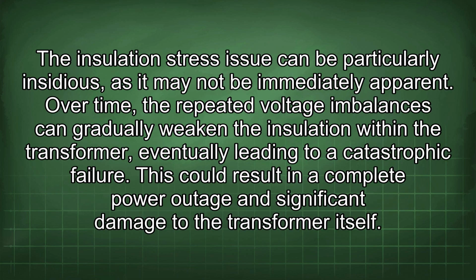The insulation stress issue can be particularly insidious, as it may not be immediately apparent. Over time, the repeated voltage imbalances can gradually weaken the insulation within the transformer, eventually leading to a catastrophic failure. This could result in a complete power outage and significant damage to the transformer itself.